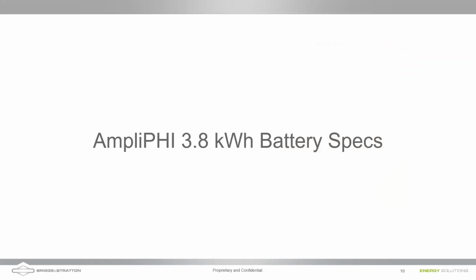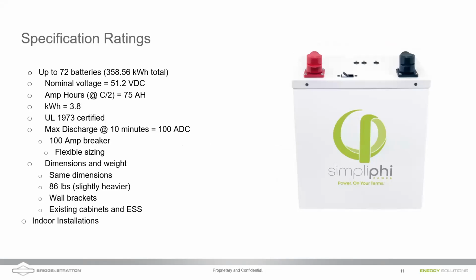Now, I did want to also bring up our SimpliPhi battery here. Our 3.8 kilowatt hour SimpliPhi battery is indoor rated, so this may be a better fit for those cold environments where you need the battery to be in an insulated environment anyway. You're not prepared to install it fully outdoors. This has a very, very similar BMS, all the same functionality. So you're looking at the same communications functionality, monitoring capabilities. Charge and discharge current ratings are a little different because you're looking at a smaller battery.